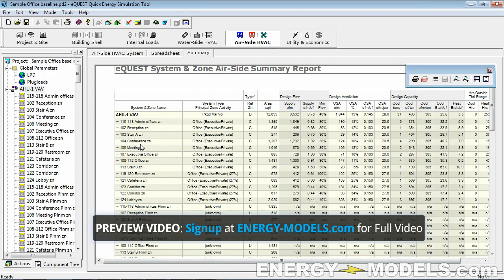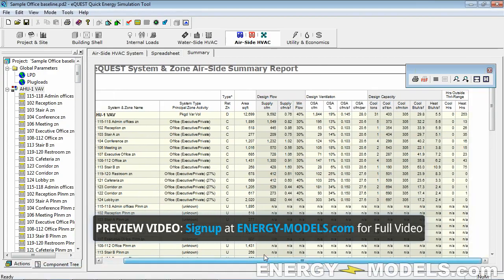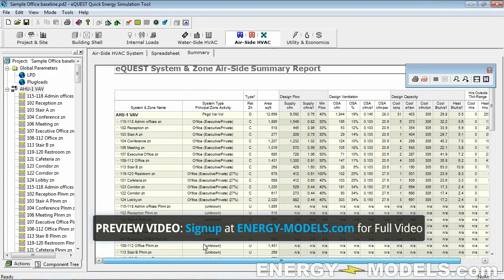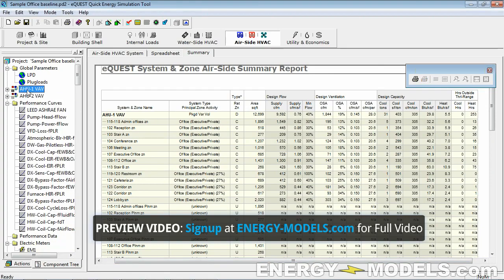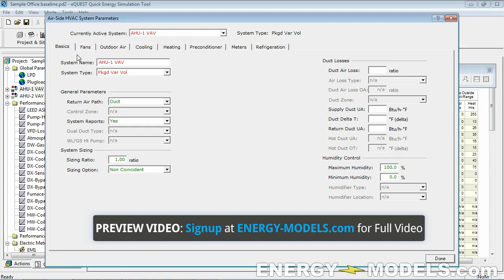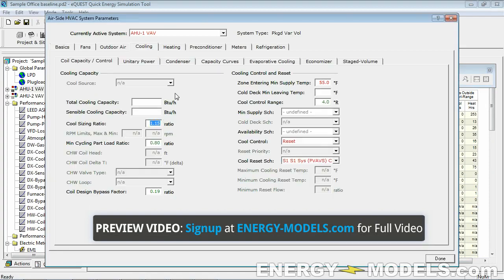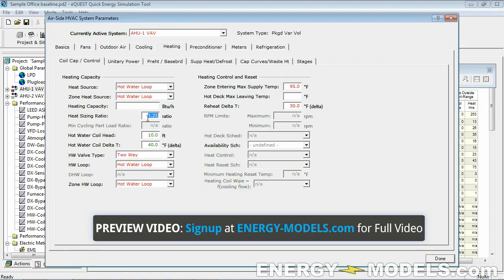What you're supposed to do to eliminate unmet hours — let's just look at one room, which is 103. What you're supposed to do is go into its system and increase this ratio. That's right out of 90.1 in 2007, and so we could just go up to 1.35. In my opinion, that doesn't really solve anything most of the time.